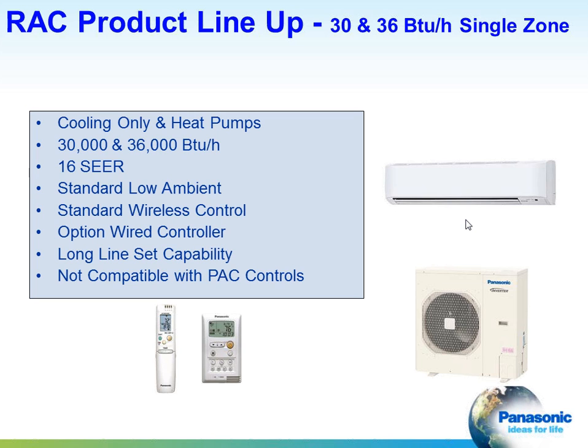And again, this would be for your IT rooms and server rooms where they might want a controller mounted on the wall. There is also long line set capability here. We can go up to 165 feet with pretty healthy changes in elevation. That's something that you want to talk with us about when you purchase the equipment or when you're selling the job. This product line, the RAC product line, has its own line of controls. We can't mix with the PAC controls that we'll talk about in a few minutes.